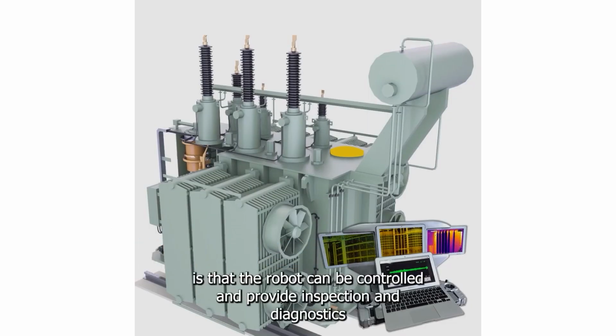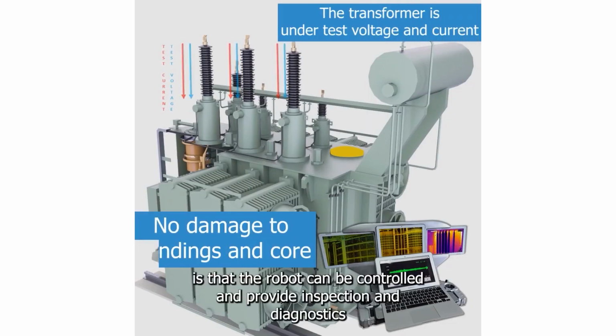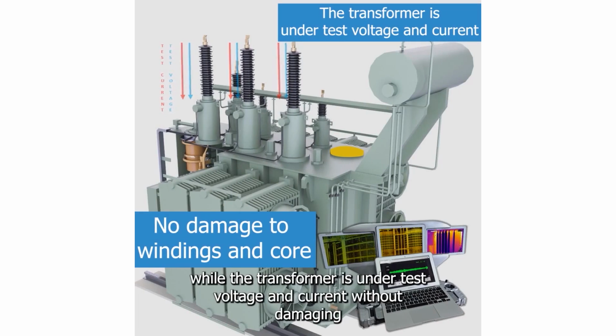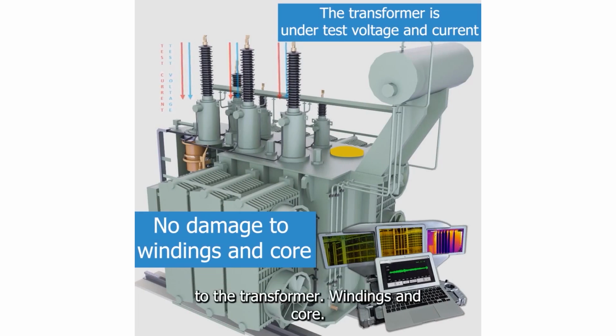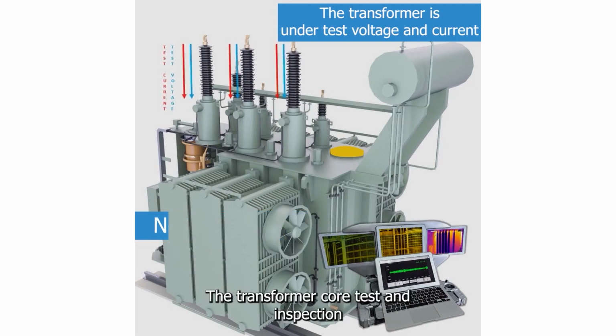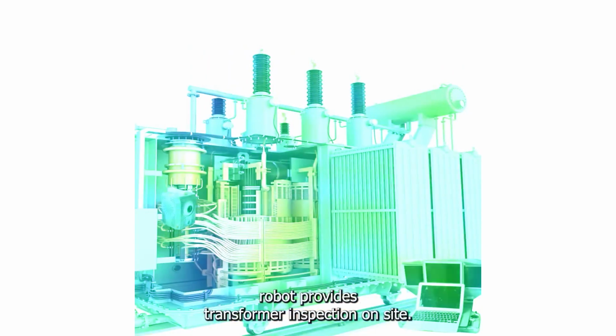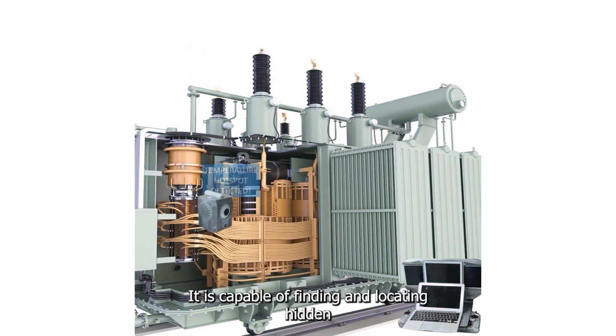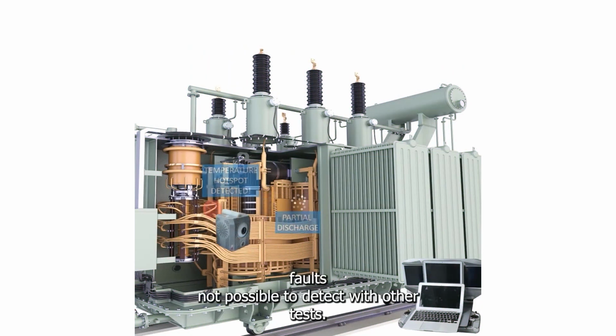Our transformer core test and inspection robot can make a fast service estimation in just a couple of hours on site without complete oil drain or shipping to service. It is the first test robot which pinpoints and evaluates transformer PD and hotspots, making it possible to make the right service decision with significant savings and reduced risk.